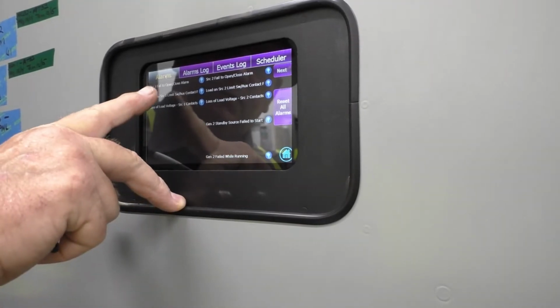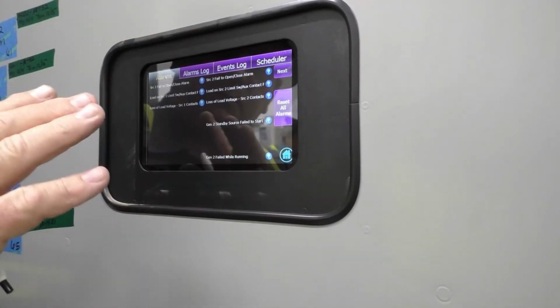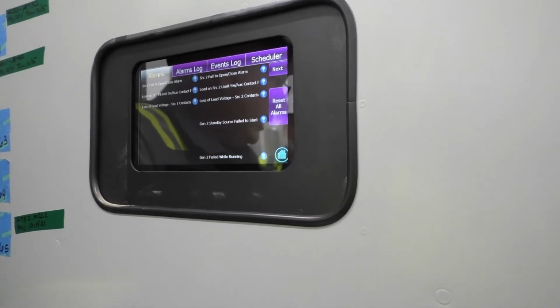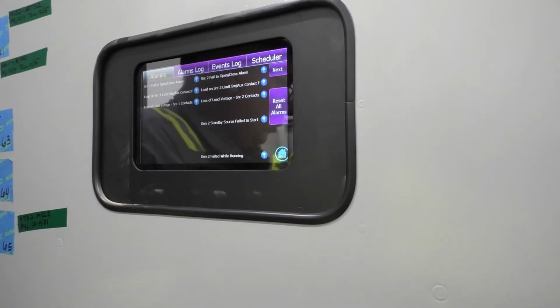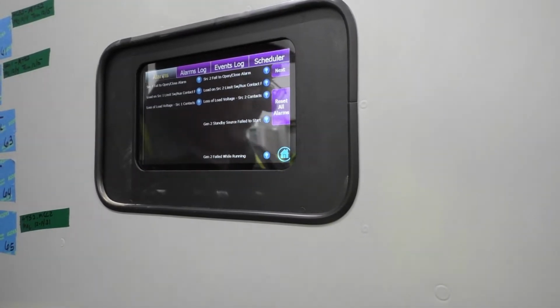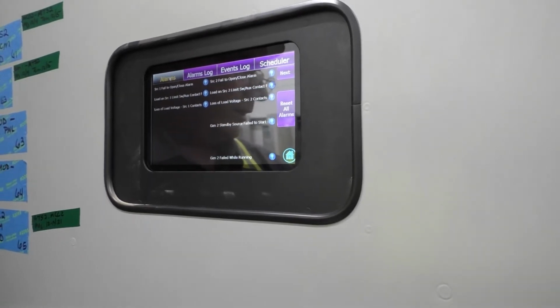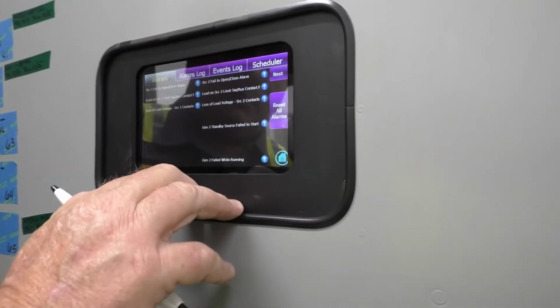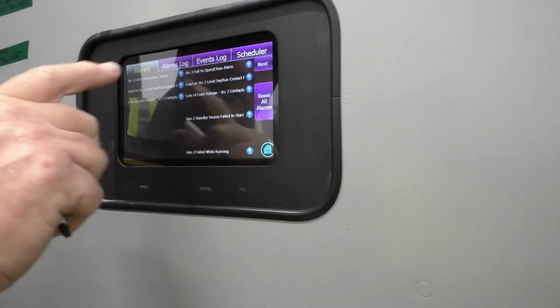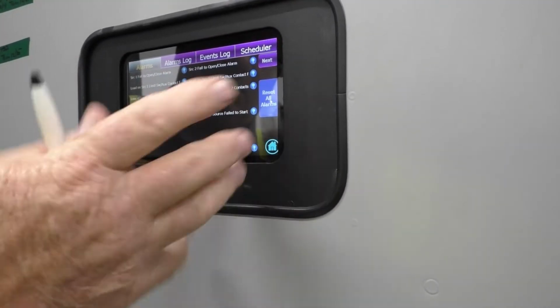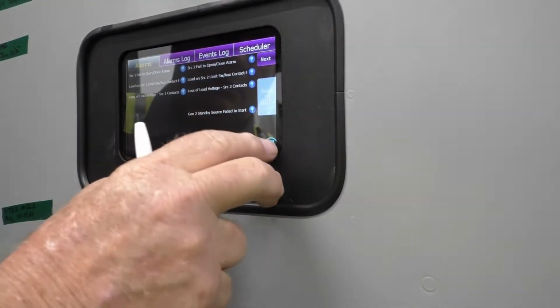It's got like source one fail to open or close. That means the breaker didn't change state. It either didn't close or open when this asked for it. We actually had that problem at the beginning. We fixed it. It's a minor wiring issue in the transfer switch. The other one worked perfect, so we didn't have any problems with it. If you have an alarm, try resetting all alarms and go back to the home screen.